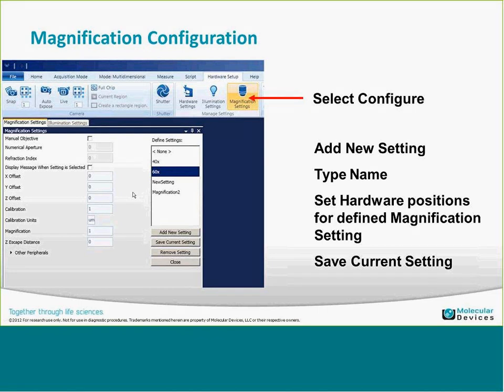Hardware settings are all the different hardware components you can control with preset values. For example, you can set an X, Y, and Z position value and call it 'Field of View 1,' then select it from a dropdown to go to that position automatically. Hardware settings are overarching above illumination and magnification — if you have the same components in both harbor settings and illumination settings, the harbor settings will override the illumination settings options.